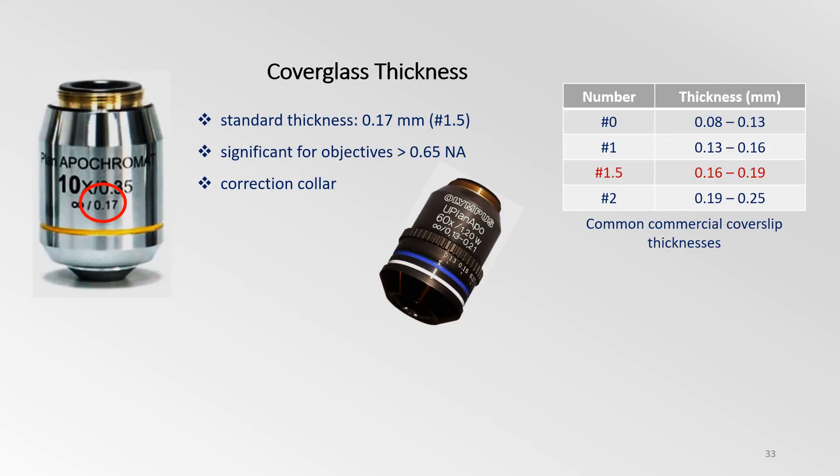The correct cover glass thickness is another important factor in optimal imaging. If the wrong thickness is used, a serious loss in resolution is expected, especially with high NA objectives. The optimum cover glass thickness of many objectives is 0.17 mm. This is commercially available as a number 1.5 or 1.5 cover glass. For some high NA objectives, a deviation of only a few microns from the standard 0.17 mm can significantly reduce resolution.